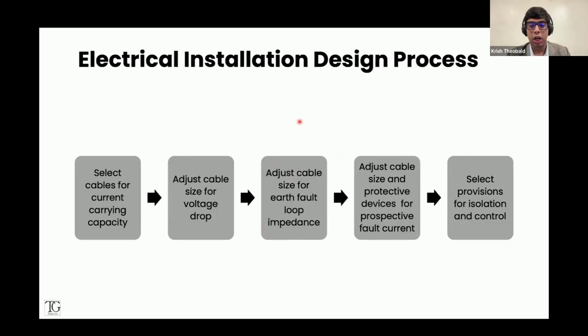We also have the cable size for prospective short circuit current. So, for example, like I said, earth fault loop impedance, you're talking about at the extremities, so minimum fault current. But towards the origin, at the distribution boards closer to your protective devices, we've got a relatively high prospective fault current, or prospective short circuit current. So it's a matter of whether our devices can interrupt that current, and when the device interrupts that current, be it your MCCB, your fuses, your circuit breakers, whatever, can the cable withstand that let-through energy? And this calculation has to be run for your entire range, from your minimum short circuit current or fault current to your maximum short circuit current and fault current.